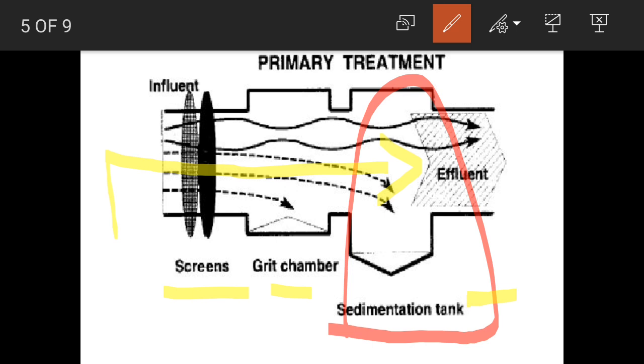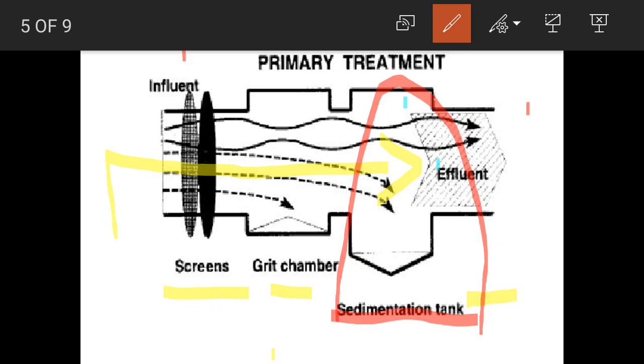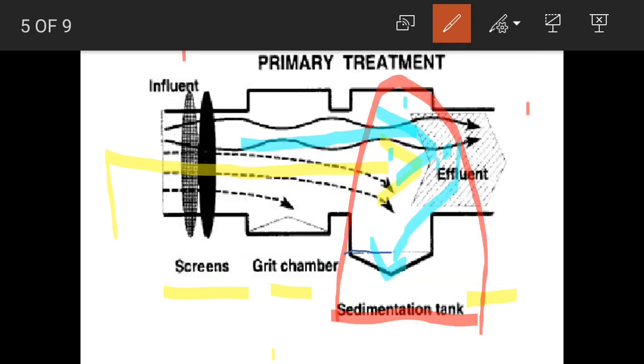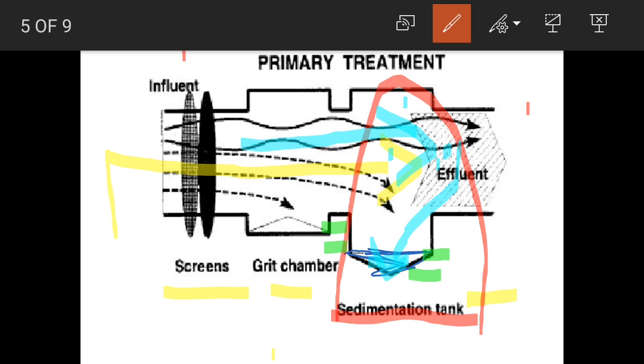In the sedimentation tank, the flow of sewage is stopped and suspended solid particles in the water are present. They settle down at the bottom due to gravity. The suspended solid particles settle down and create sludge. In the sedimentation tank, two arms are present — one at the bottom and one at the top. The sludge created at the bottom is removed with the help of the bottom arm and it is then entered into the digestion tank.